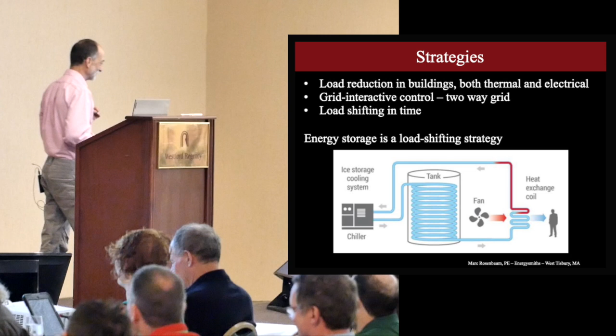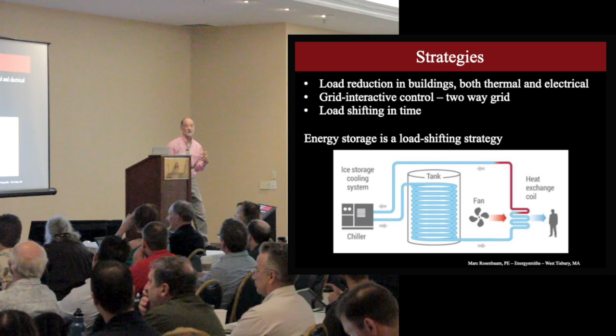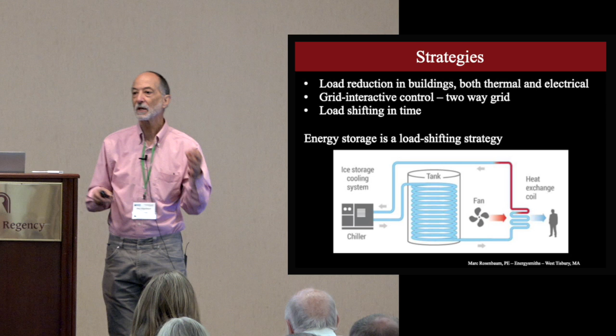When you store ice, you're able to run your coils colder. If you do loads for very energy efficient buildings, like passive houses, you find they're all cooling load dominated, even in places where people probably shouldn't live, like Duluth. The colder the coil, the more moisture you get out, and your sensible heat ratio shifts. I think we have an emerging issue in more efficient buildings with cooling: the sensible load keeps driving down with better glass, better lighting, and so on, but we haven't done much about the latent load, because people are still breathing in the building, cooking, and taking showers.